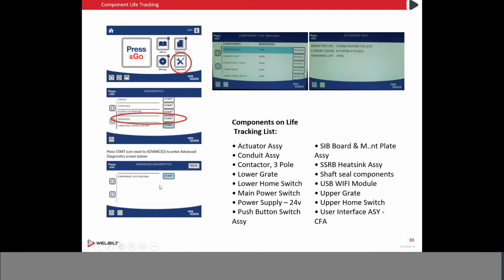The motion test just moves up and down between the upper and lower home switches at different voltage rates for different speeds to see if it gets to where it needs to be within 40 seconds. And then your temperature test is just testing the rise in temperature and making sure it gets done before it times out. So again, when you go into your component life tracking, make sure that, as you see here, remaining life is 100%, and then details, and then you go ahead and reset it from here.